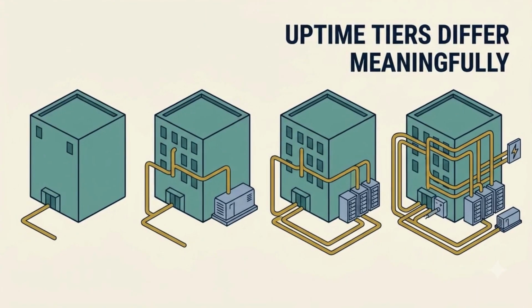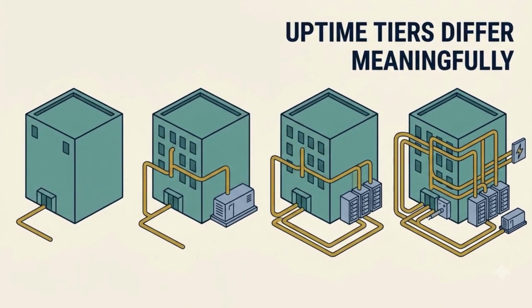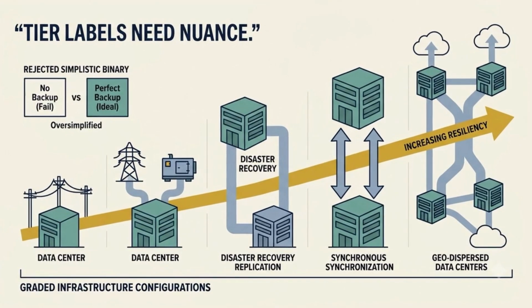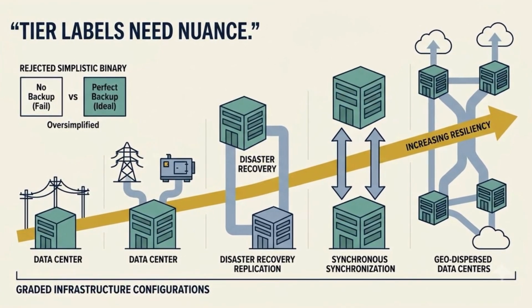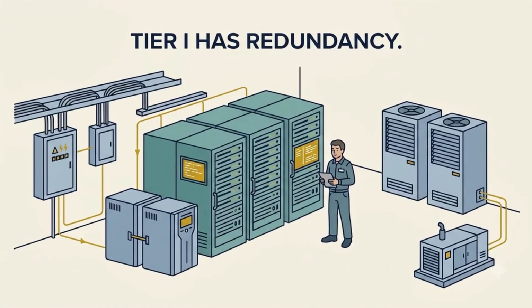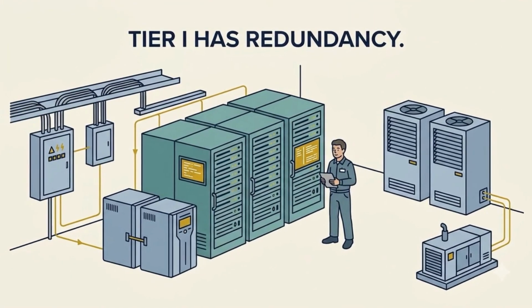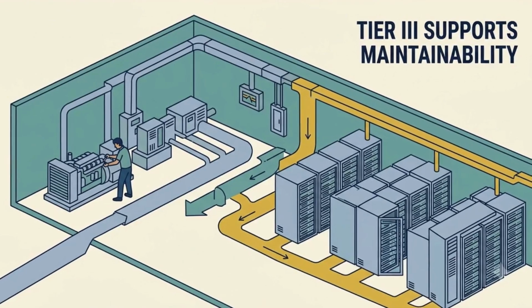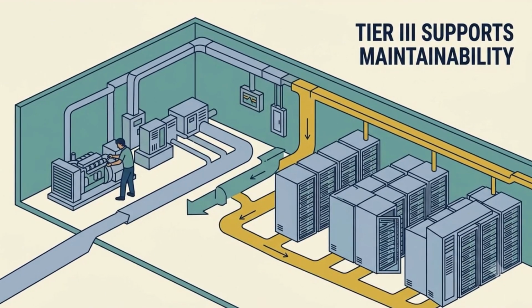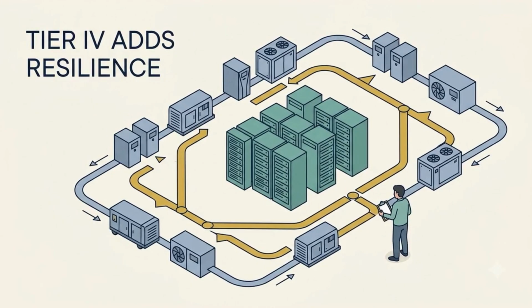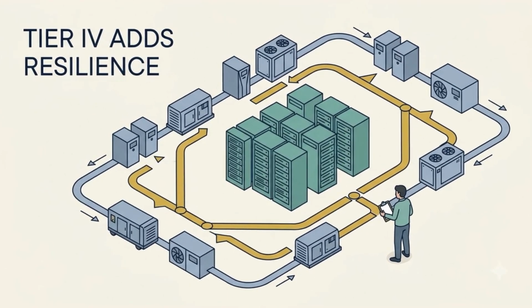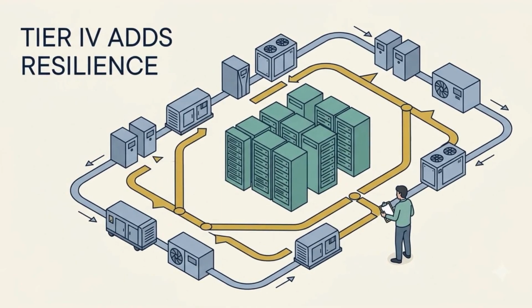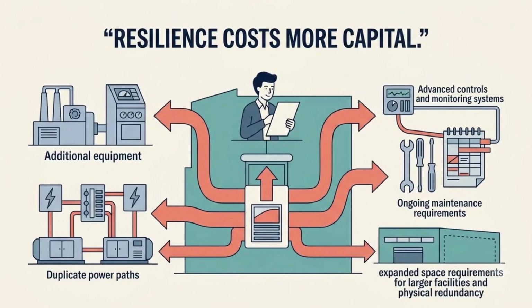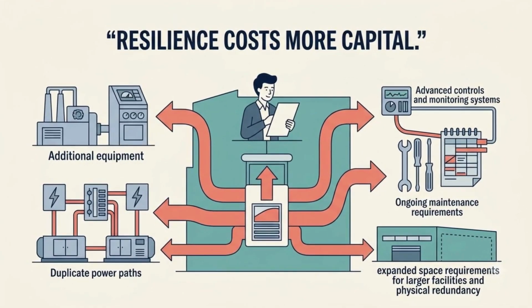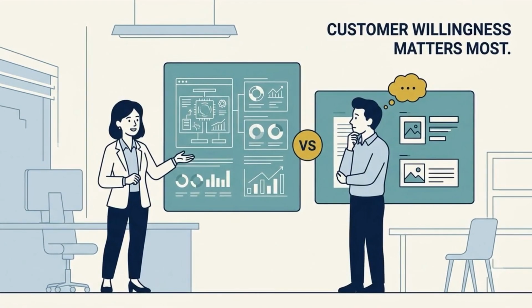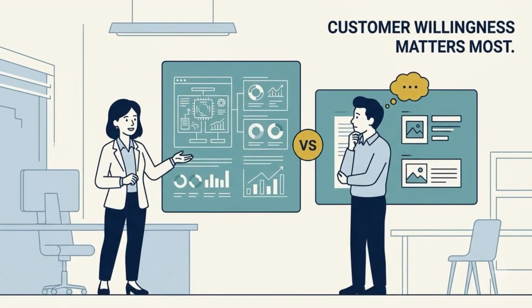Reliability has similar economics. The Uptime Institute's tier system runs from Tier I through Tier 4, but the categories should not be reduced to no backup versus perfect backup. Tier I already includes basic dedicated infrastructure, such as UPS capacity, cooling, and an engine generator. Tier 3 is designed around concurrent maintainability, while Tier 4 adds fault-tolerant characteristics. Higher resilience can support customers with more demanding uptime requirements, but the owner pays for additional equipment, paths, controls, maintenance, and space. The important business question is not whether the highest technical specification sounds impressive.